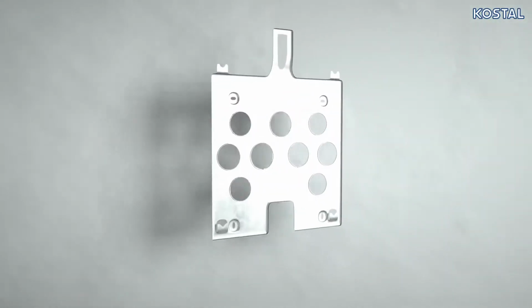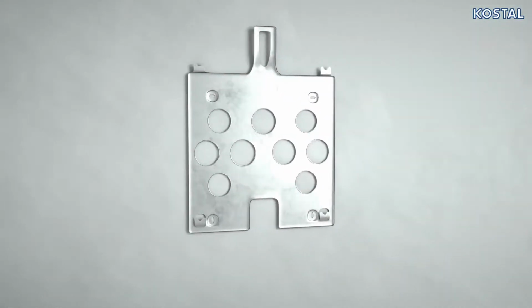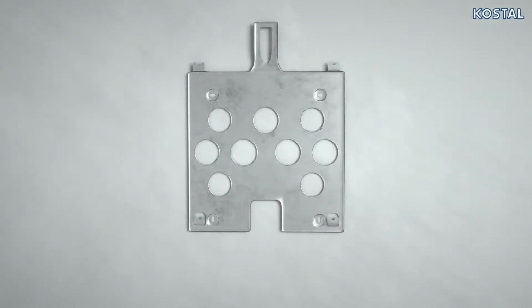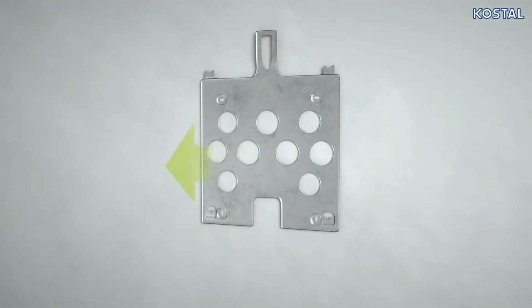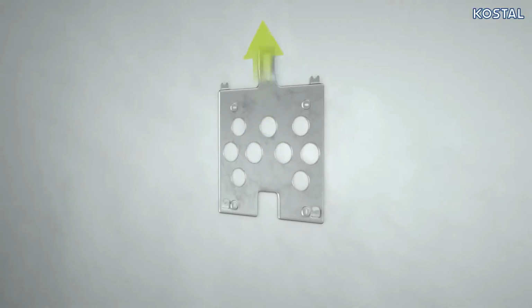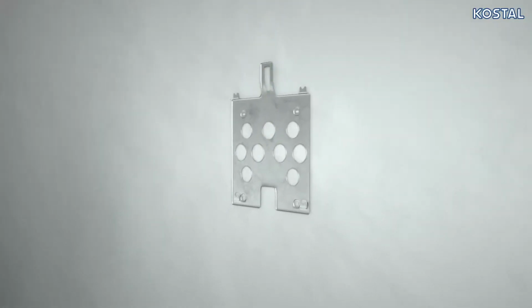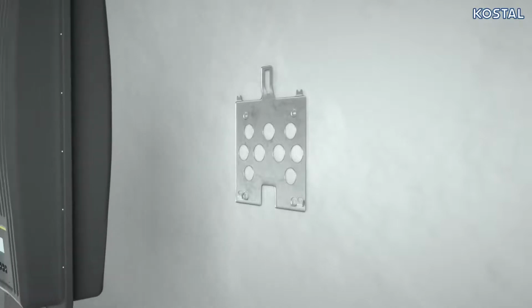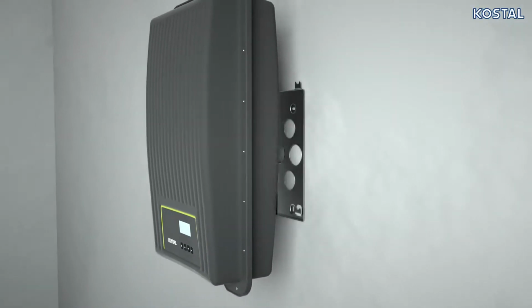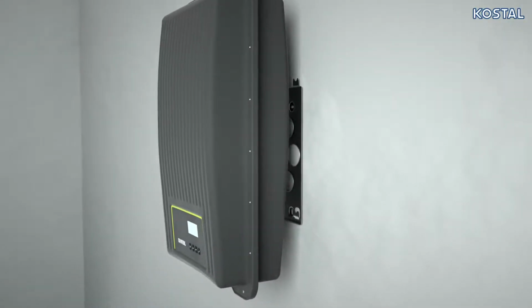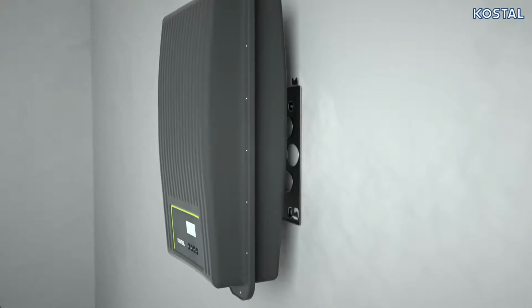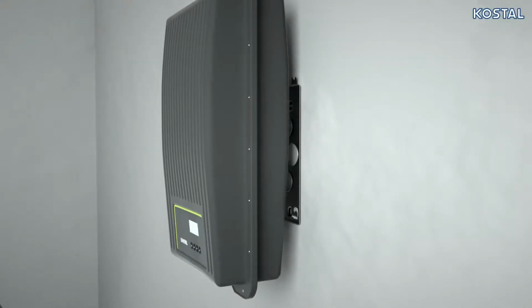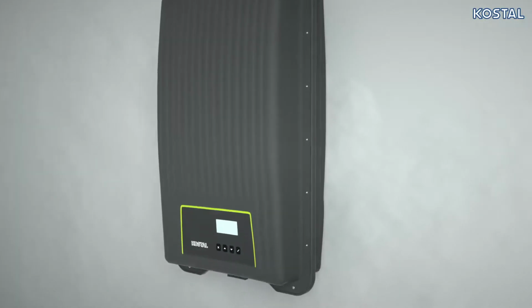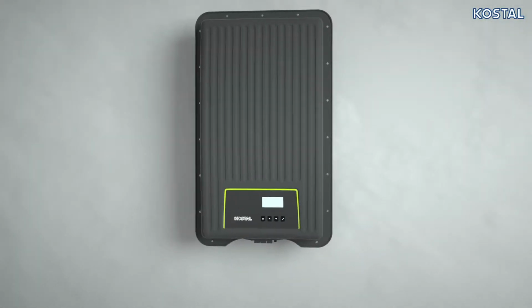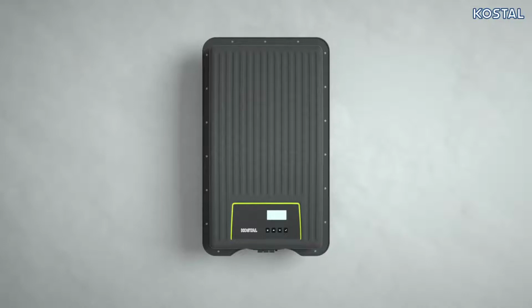Fit the installation plate vertically on a level installation surface. Ensure that the lateral metal strips are facing forwards and the locking plate is facing upwards. Position the PIKO MP Plus centrally on the installation plate. Hang the 4 locating pins on the rear of the inverter into the locating tabs and gently apply pressure to the device. Lower the inverter until the installation plate's locking plate audibly engages.